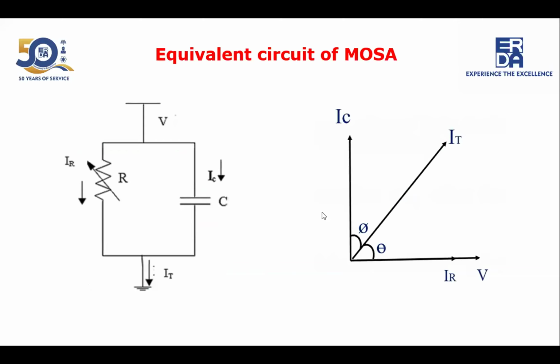So if we see the equivalent circuit of the MOSA, the metal oxide surge arrestor, there are two parallel paths. One is the resistive component and another one is the capacitive. Since there are two parallel paths, the current is also divided into two parts, the resistive current as well as the capacitive current. Whatever current passes through the surge arrestor, we normally call the total leakage current. It is divided into two categories, IR and IC.